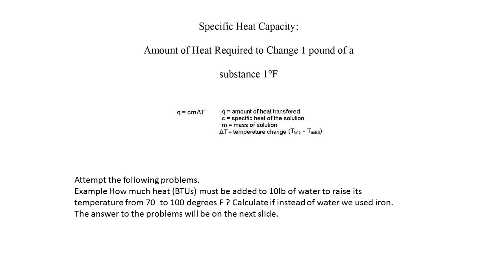When finding the amount of heat in a substance, what we are doing is calculating how much heat was added or removed to bring the substance to its final temperature. The formula for finding the amount of BTUs that are transferred is to multiply the specific heat capacity of the substance by the mass, which is its weight, and by the temperature change of the substance.